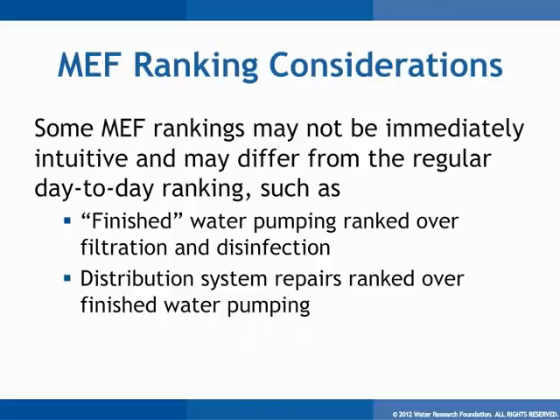It is important to undertake a serious brainstorming of the ranking of MEFs, as an appropriate BCP ranking for recovery from a disaster may differ from the normal day-to-day perspective. For instance, in a utility in a seismically active area, the greatest threat may be an earthquake with many main breaks in the distribution system — in that case, the utility might consider damage assessment, system isolation, and main break repairs more immediate than water production and pumping. In a utility that will pump untreated water in the distribution system for fire protection and sanitation, finished water pumping may be ranked above filtration and disinfection. There is no one-size-fits-all for MEF ranking; each water utility must identify and rank its MEFs based on the nuances of the individual system.